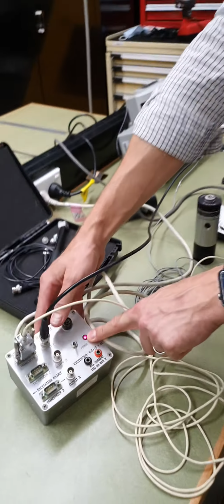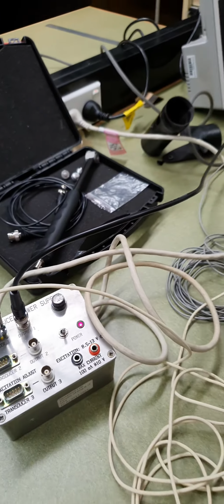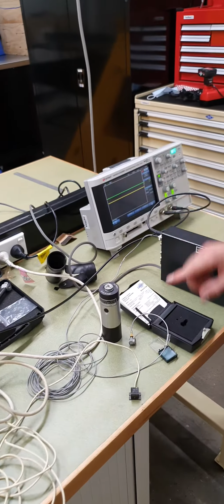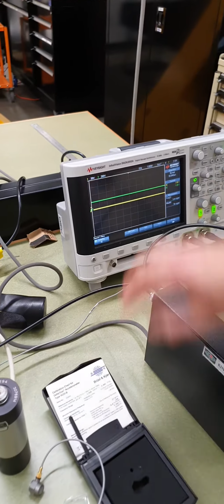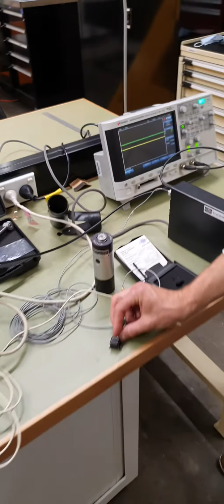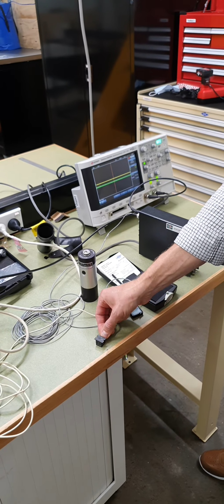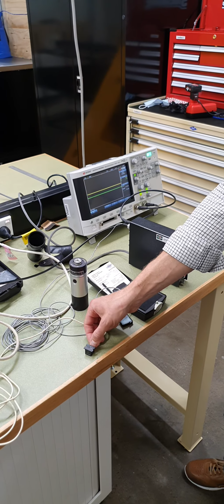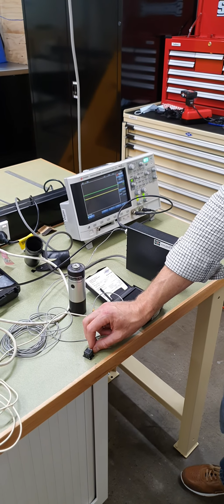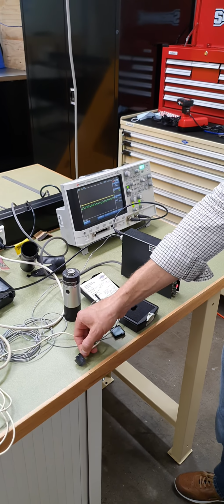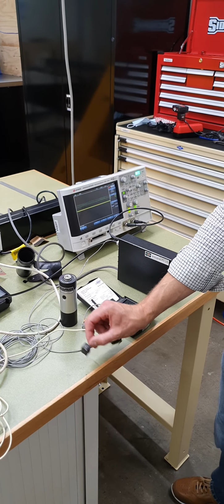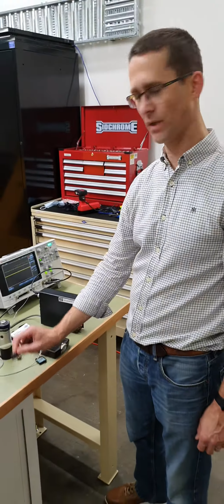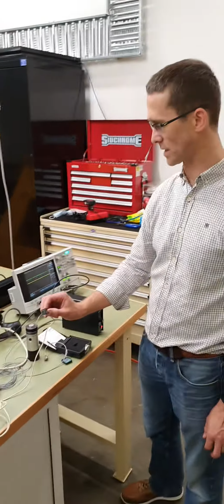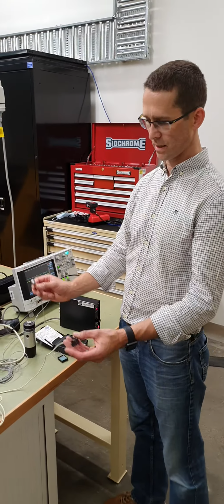Here you can see I didn't have it powered up, so we weren't getting a signal on the oscilloscope. Now we have a signal. This is essentially 1G. If I turn this upside down, you'll see that I get minus 1G when I invert that transducer. 1G, minus 1G, plus any vibration that I apply to that transducer. Okay, so that's a DC measurement, DC acceleration measurement, AC acceleration measurement.